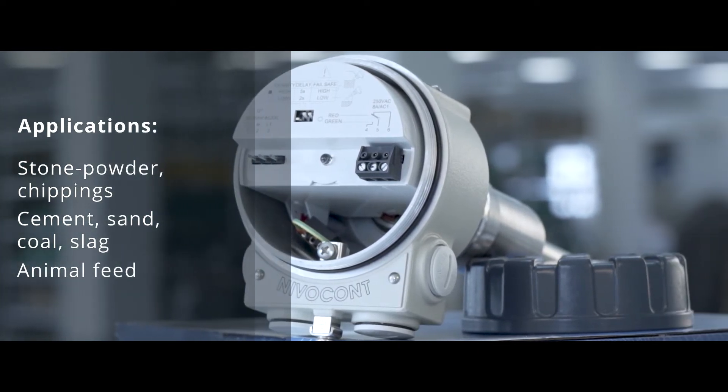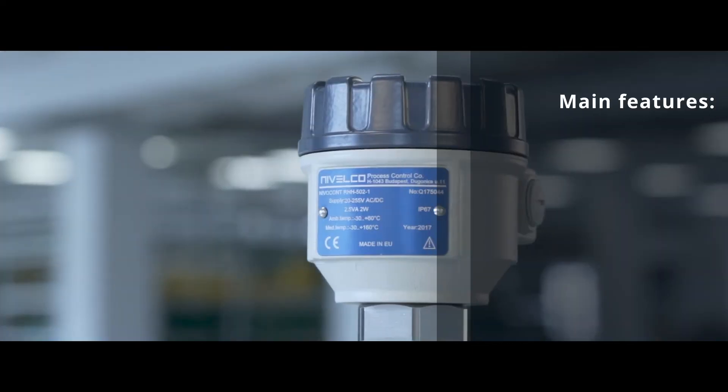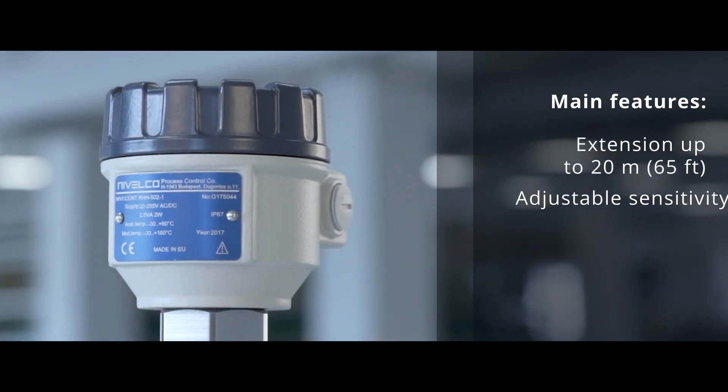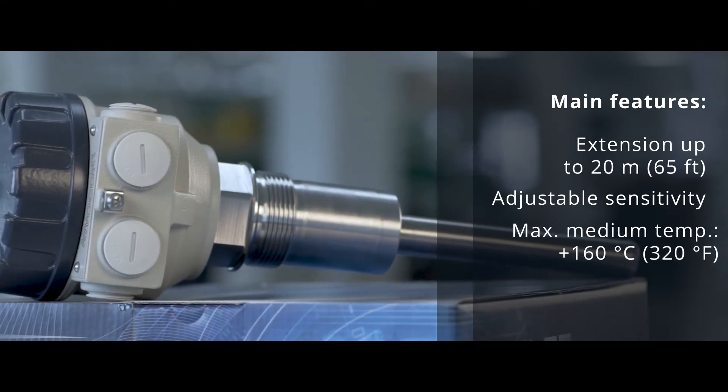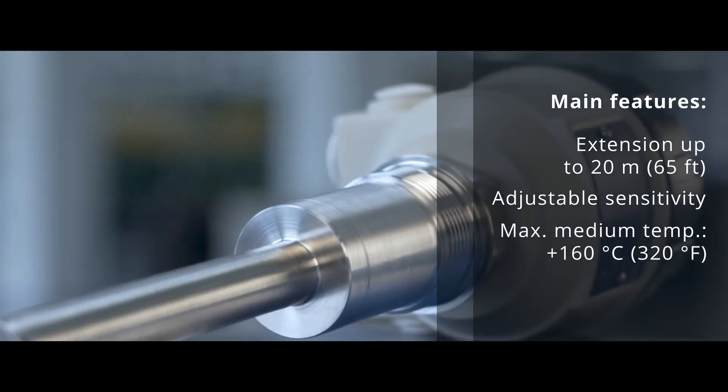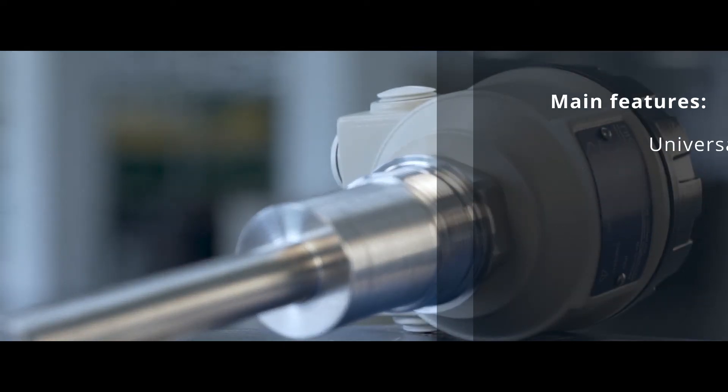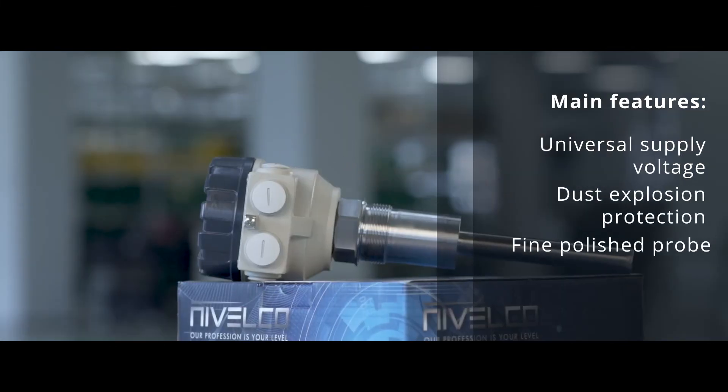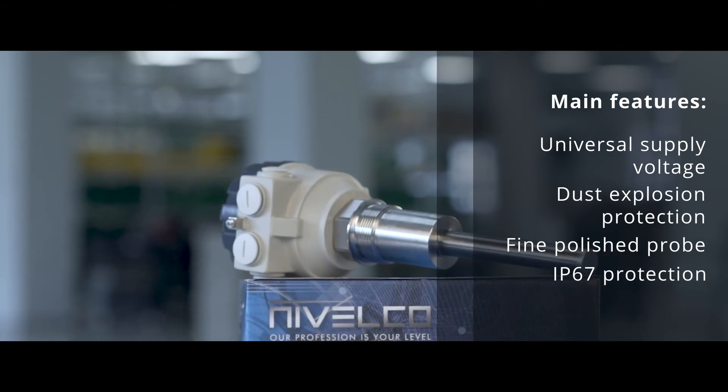Animal feed. The main features of the instrument are the following. Extension up to 20 meters. Adjustable sensitivity. Maximum medium temperature 160 Celsius degrees. Universal supply voltage. Dust explosion protection. Fine polished probe. IP67 protection.